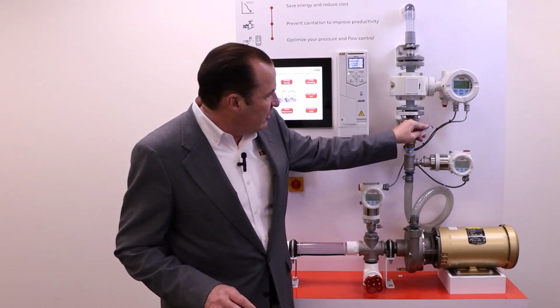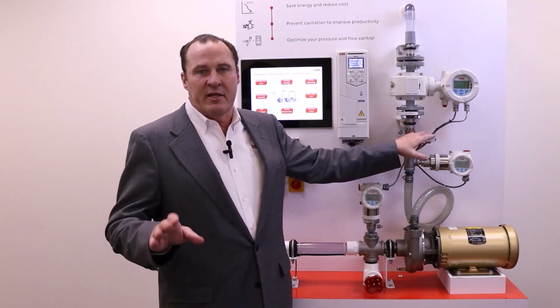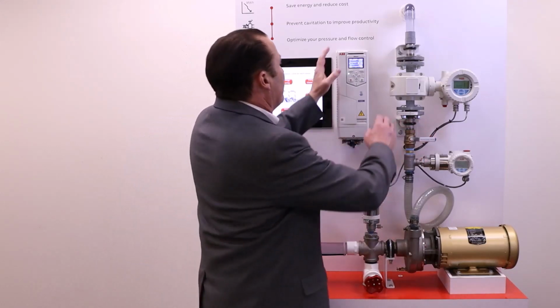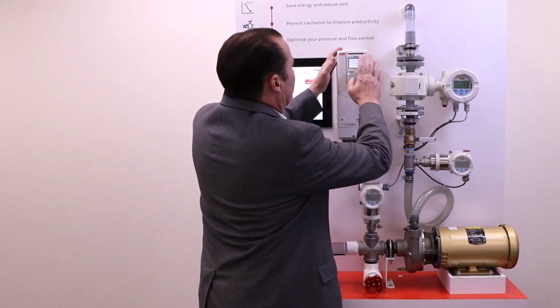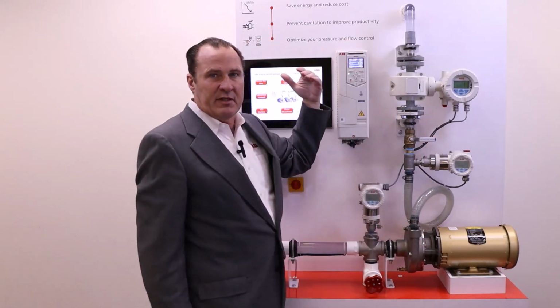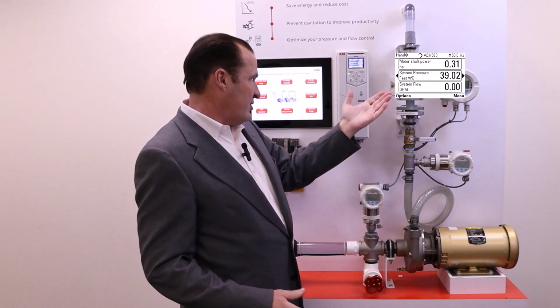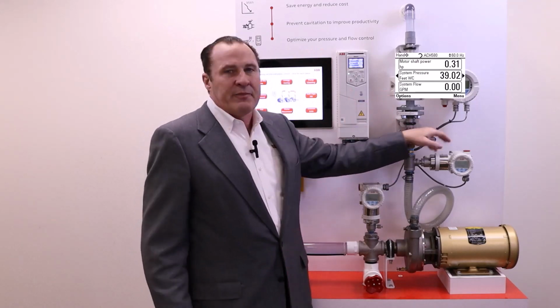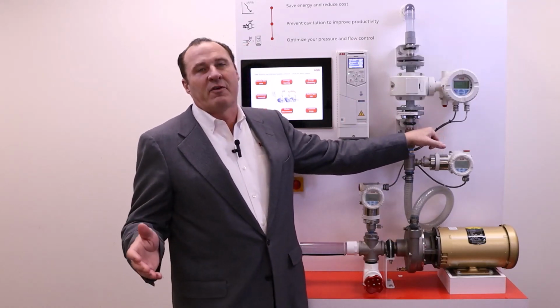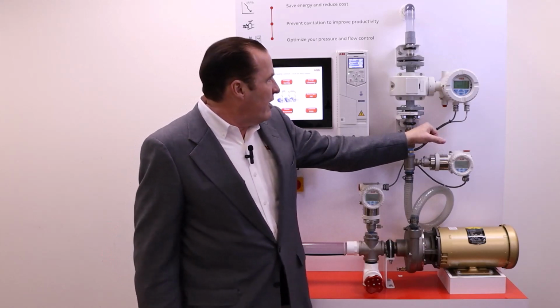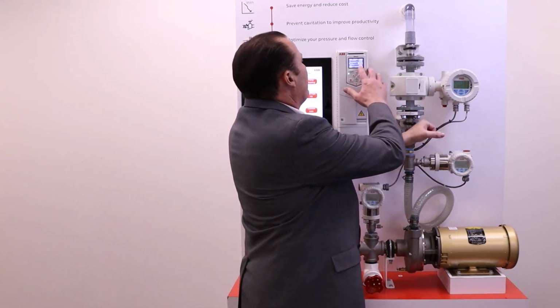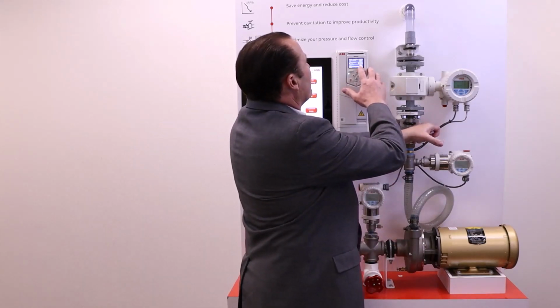I'm going to go down to a closed valve scenario. That's data point 1. I'm going to use the left and right key and the up arrow to do a screenshot to save the data from the screen, and we'll do some magic editing and show it right here. Now, the next data point is 4.22. So I open the valve up until I get a flow of 4.22.